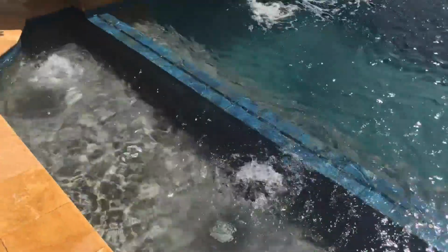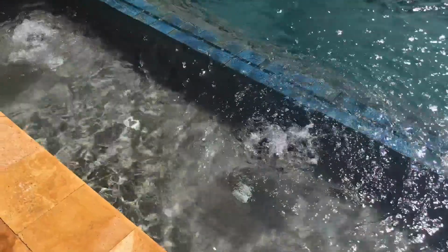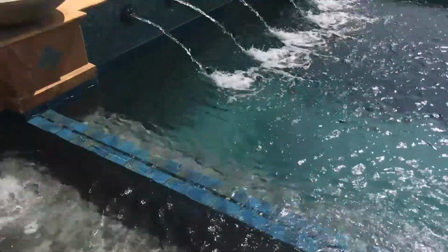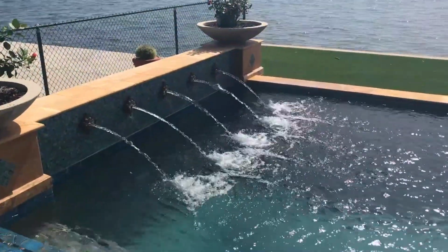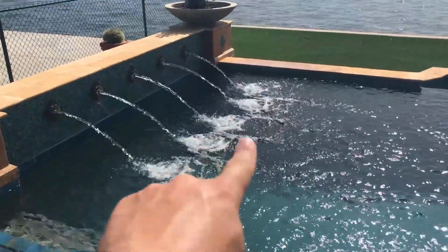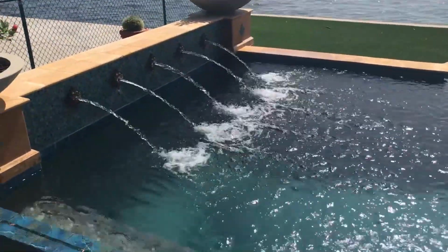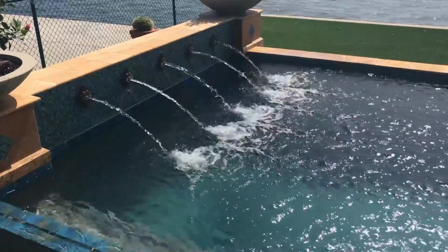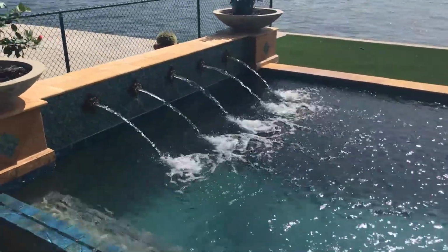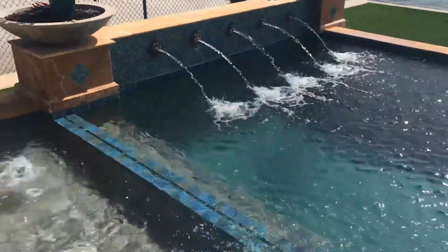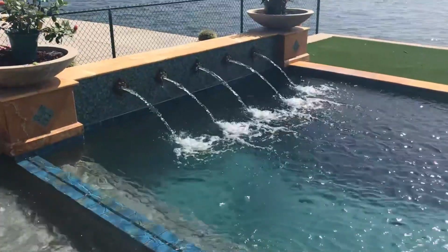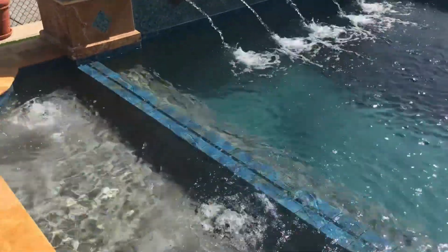So here's another example of the aeration process. You see these water features here in this little kiddie pool that's attached to the main pool, and then you see 5 water features here that are creating all the turbulence and all the bubbles out there. That's all causing that carbon dioxide to gas off. It's going to raise the pH. So if you're fighting high pH, turn those off, and if you're fighting low pH, turn them on and let them do what they're doing, and that will raise the pH naturally.